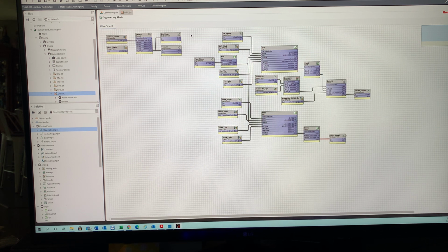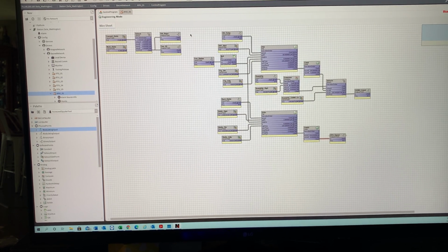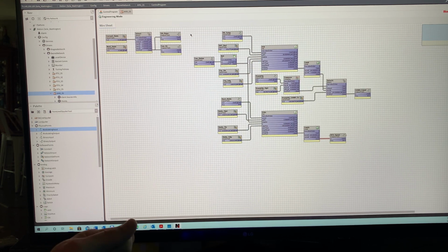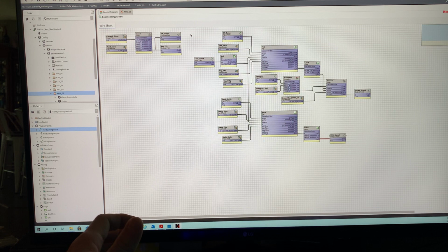If the output is working and you connect the wiring back up, we like to take the wiring off the actuator and verify the voltage going into it, because sometimes you're sending a signal but get a funky reading since the actuator itself is bad internally and might be shorting. It's a process of elimination—don't get overwhelmed seeing 100 different wires. Take it piece by piece, just like following a schematic on an RTU, an air handler, VFDs, all that good stuff.